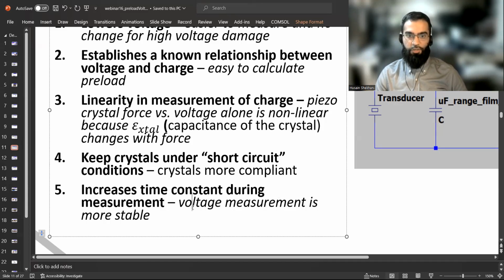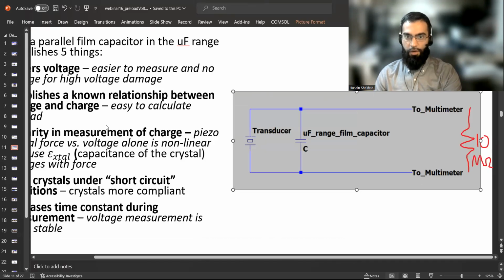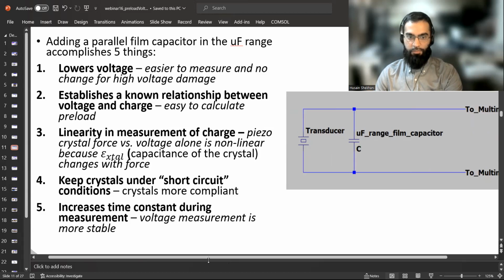It increases the time constant during measurement. So you have this capacitor, and if you're measuring voltage with a common device like a multimeter, it has a 10 mega ohm impedance. Whatever load you connect, that capacitor will leak through this 10 mega ohm resistor. If you're just measuring the transducer itself with a load, you would not be able to measure this with a normal multimeter, because if you had, say, 1 nanofarad and 10 mega ohms, the charge would just run out instantly and you would not be able to measure much of anything. So having a microfarad film capacitor at that high level also makes the voltage measurement more stable, and you can measure it with an ordinary device.